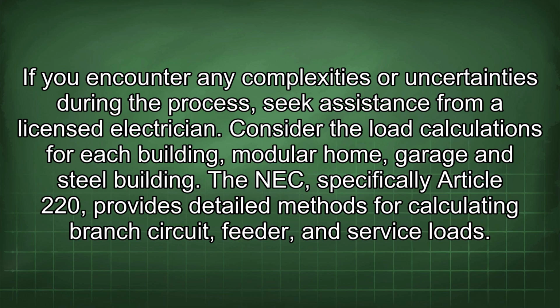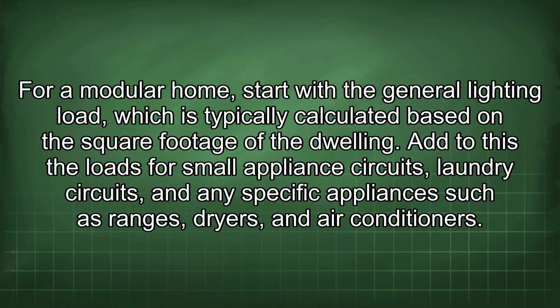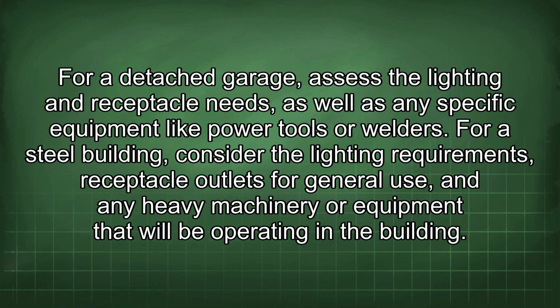Consider the load calculations for each building, modular home, garage, and steel building. The NEC, specifically Article 220, provides detailed methods for calculating branch circuit, feeder, and service loads. For a modular home, start with the general lighting load, which is typically calculated based on the square footage of the dwelling. Add to this the loads for small appliance circuits, laundry circuits, and any specific appliances such as ranges, dryers, and air conditioners. For a detached garage, assess the lighting and receptacle needs, as well as any specific equipment like power tools or welders.